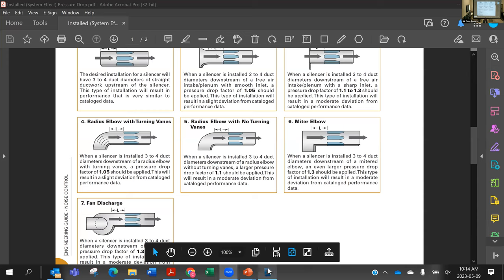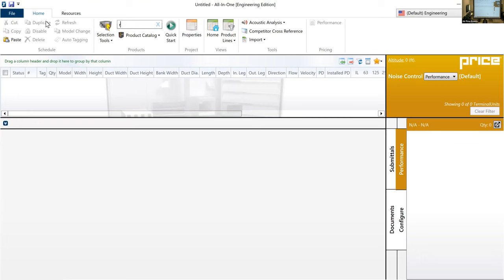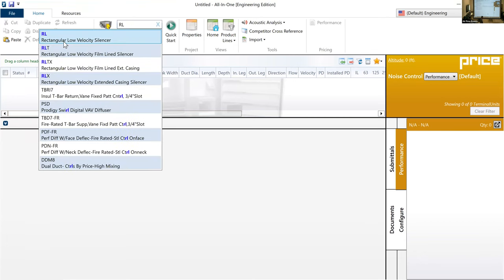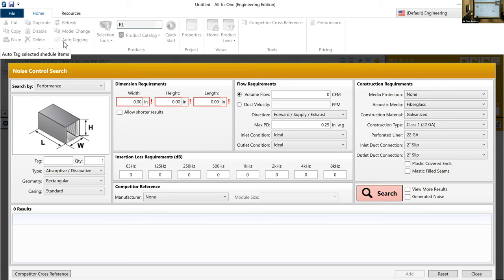What I mean by that is, when you're selecting a silencer, I'll jump in here to our software. If I go to our silencer selection screen, you may or may not be familiar with our all-in-one tool. When you select a silencer of whatever dimension, say 24 inch by 24 inch by 60 inches, the conditions in which the silencer is installed are one of the factors you can select. They default to being ideal, which is basically 3 to 4 duct diameters of empty duct. So straight, unobstructed duct right before and right after. Which is never the case.